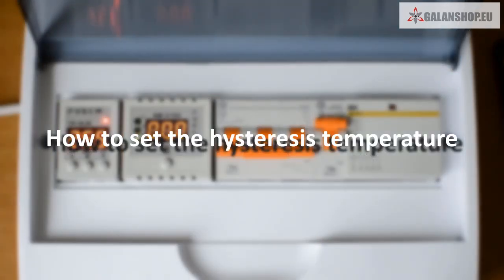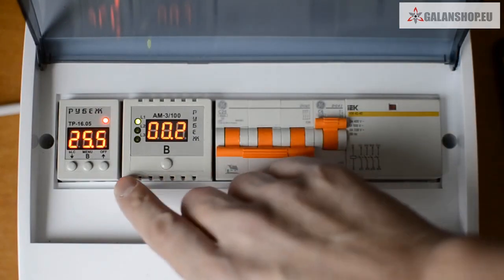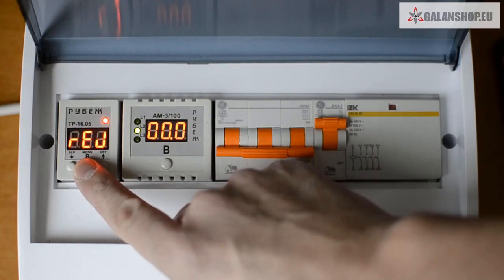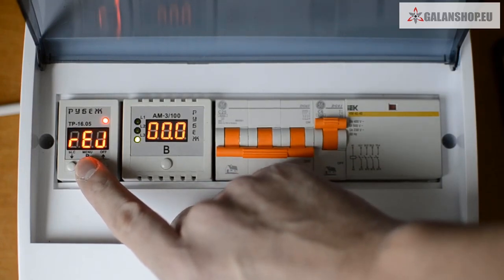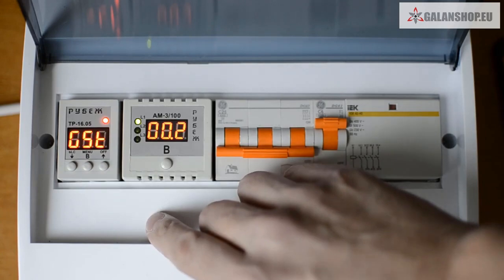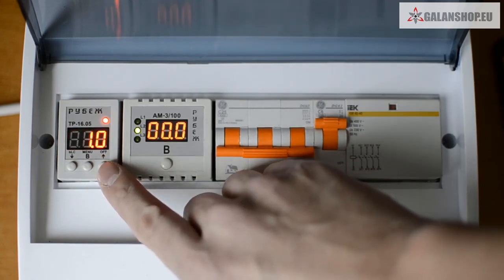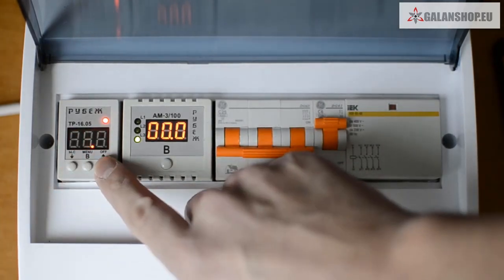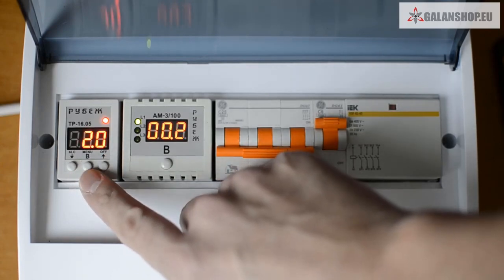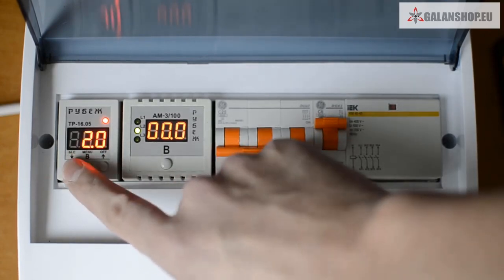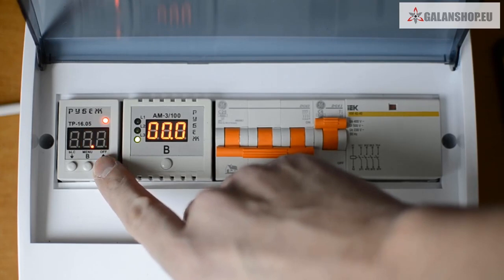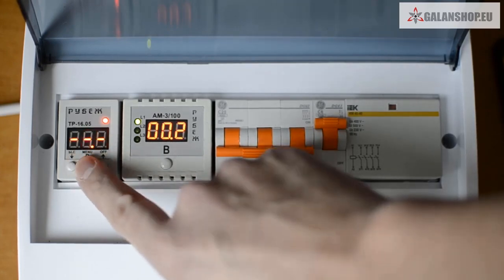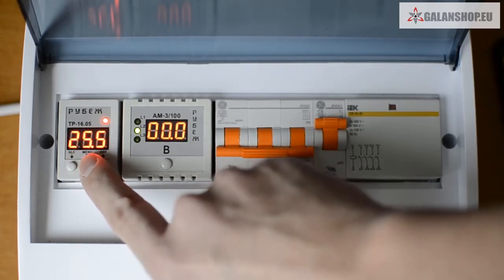How to set the hysteresis temperature. First, we need to open the menu. Press the button B and hold it for 2 seconds. Then press shortly the same button. Select the hysteresis submenu. Then press any of these 2 buttons to set the required hysteresis value. The default value is 1 degree. Let's say we want to set it to 2 degrees. To confirm it, we press the B button.